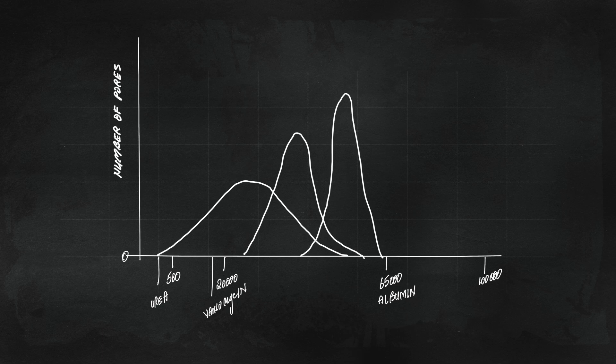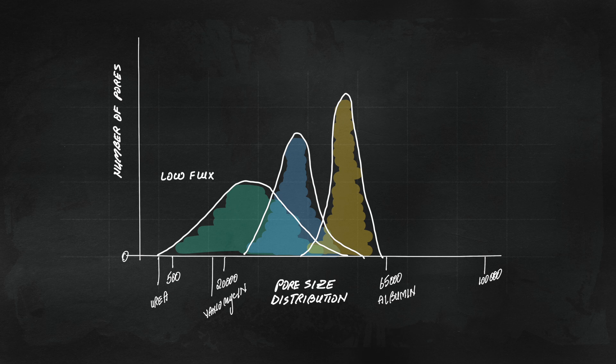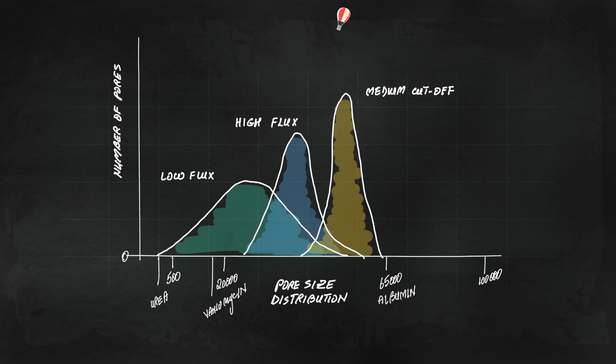The main determinant of a particular dialyser's handling of solutes is the pore size distribution. Low flux membranes have low ultrafiltration coefficient, typically less than 15 mL per mmHg per hour, such as the cellulose or cuprophan-based membranes. Whereas the high flux and the medium cutoff membranes have larger pores, with the medium cutoffs having narrow distribution of large pores.